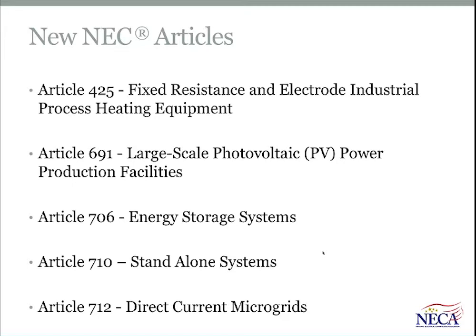We also see 3 articles in Chapter 7, and when you see something in Chapter 7, you should automatically think system. It's not just equipment, like battery, for example. That would fall under Article 480 as equipment. Battery certainly is one component of an energy storage system. But 3 new articles that were the result of 6 years worth of work. That's 2 NEC development cycles. Article 706 dealing with energy storage systems. 710 deals with standalone systems that are islanded systems, not grid connected, off grid. And then Article 712, direct current microgrids.